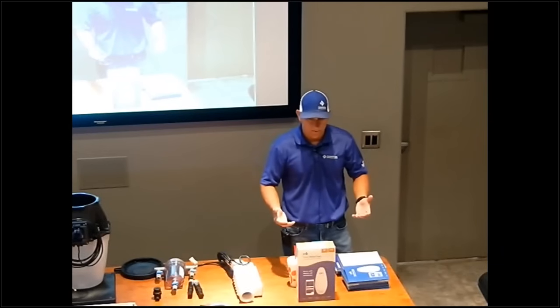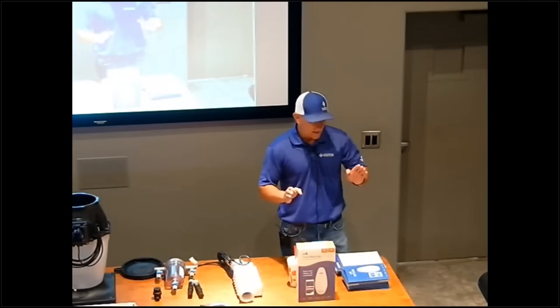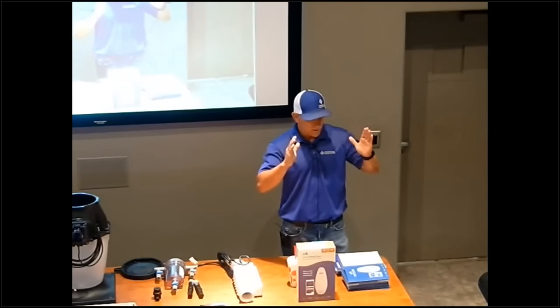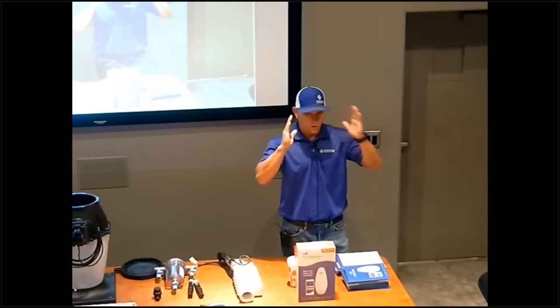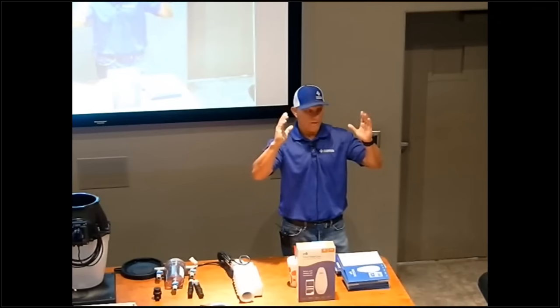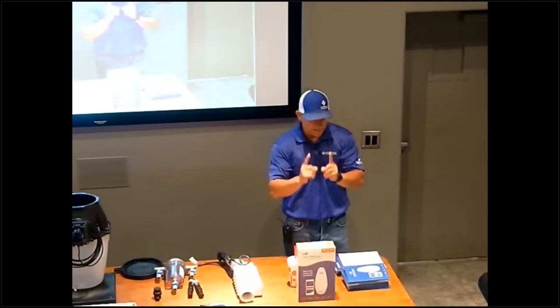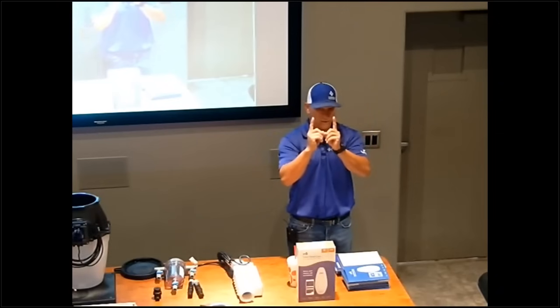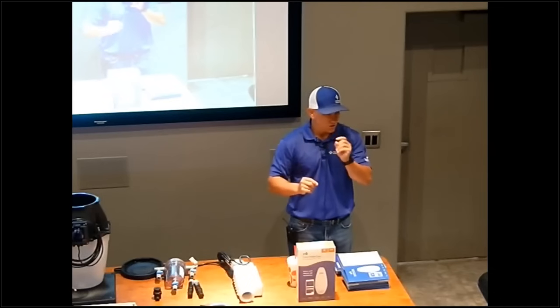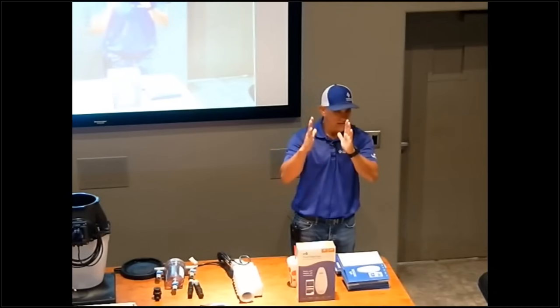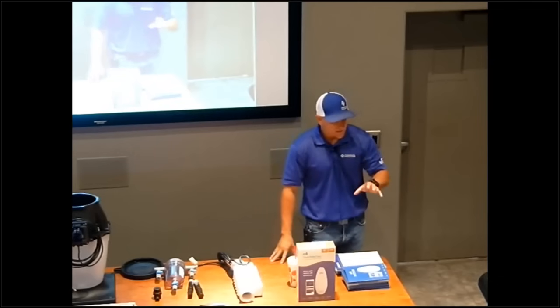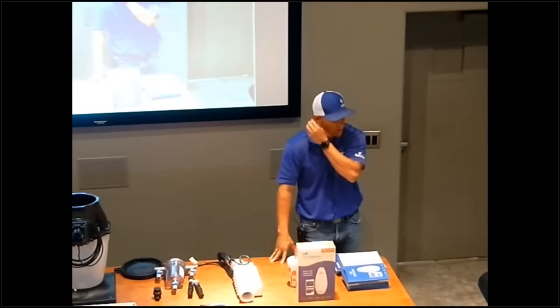So what I'm getting at is set your low speed for one big window, say 12 a.m. to 8 a.m. Then take your high speed and set it inside that window, so set your high speed at 4 a.m. to 8 a.m. The reason I say that is the high speed takes priority.